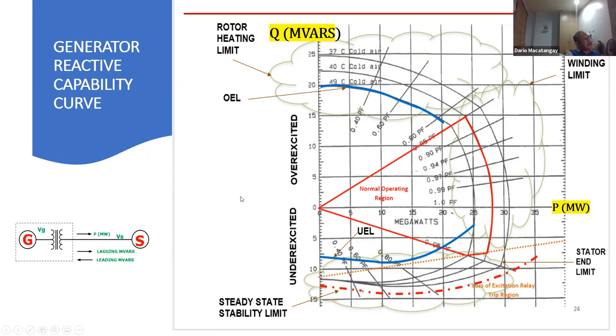We have what we call a reactive capability curve, and this is a generator reactive capability curve. The generator manufacturer would supply this information to you. As you see here, you have two components: the true power, real power, megawatts, which is used to support the heating, lighting, anything that requires true power. Again, I already discussed megavars here. If you are operating from zero up here, it's called overexcited. You put more excitation to the generator, you increase the magnetic field requirement, and therefore you are producing what we call lagging megavars.